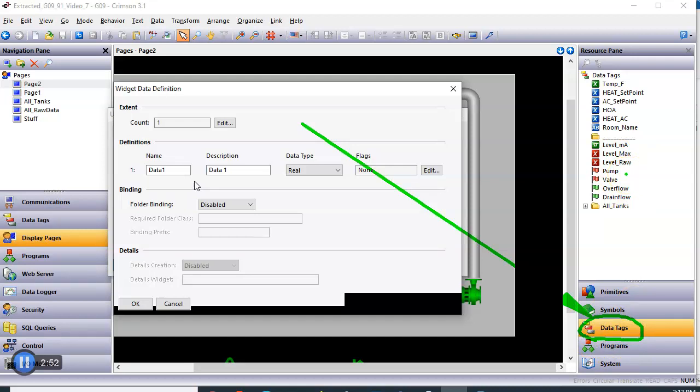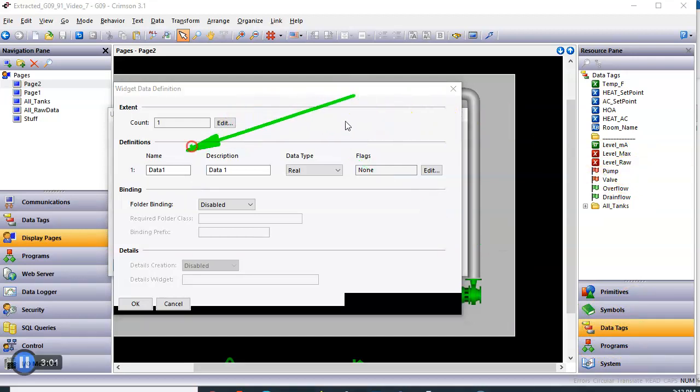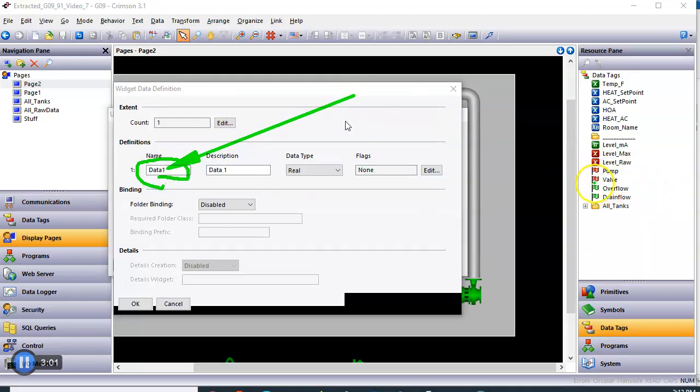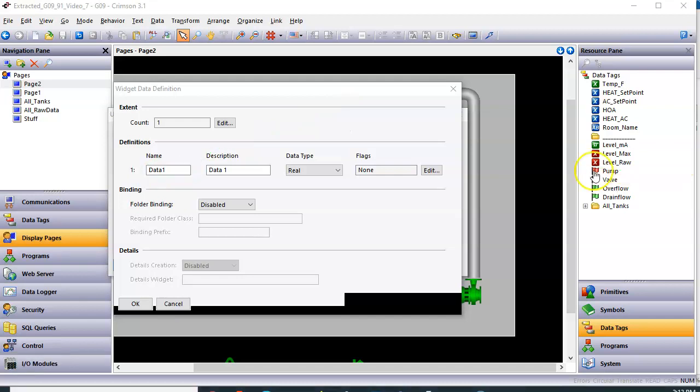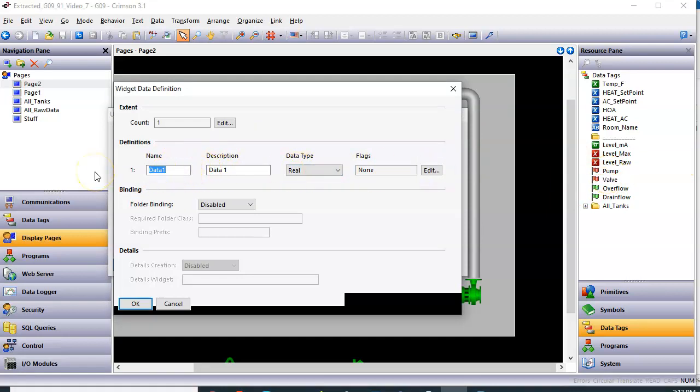One thing I like about Crimson is at this juncture, it lets you see all of your tags. Now I am going to name the widget tag. I'm going to name it the same as this tag here, because later on we're going to have all these tags and folders. So where it says name, I look over here and see the name of the tag is pump. So I'm going to manually type the word pump here. It doesn't have to be capitalized the same, but it has to be spelled the same.